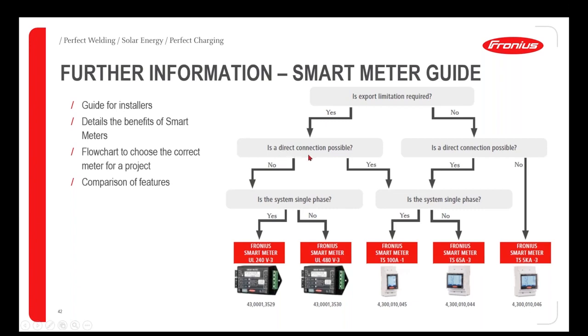If you can't do the direct connection, maybe there's no space in your consumer unit, so you want to use a CT meter, that's fine. We follow through and come down to the UL smart meter, which we saw briefly earlier. But we're expecting to see most people are going to move across to the TS100. It's so much cheaper, it's nice and tidy installation, it's simple to install, less chances for making mistakes during the install process. So we're expecting to see this TS100 becoming the primary choice for single phase installations.